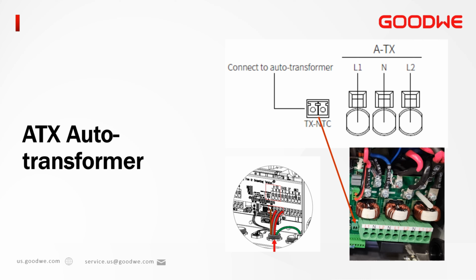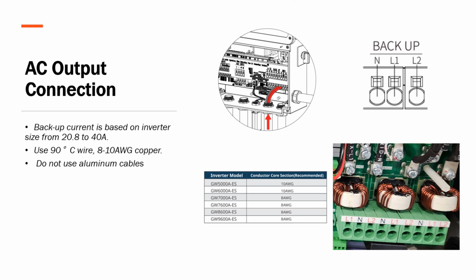If you look at the AC wiring connections, the far left L1, neutral, and L2 are intended for the ATX and are labeled on the plastic cover. You will also need to connect communications wires using the included 2-pin connector to the left of L1, highlighted on the screen by the red arrow. The output or backup side of these inverters is in the middle of the wiring block. Please follow the order for the neutral, L1, and L2 as shown on the template. The terminal will accept from a number 8 to a 10 copper wire. From here, you will need to go to an essential load panel, with an inverter output breaker based on the size of the inverter. Essential load panel or output breakers are not included.